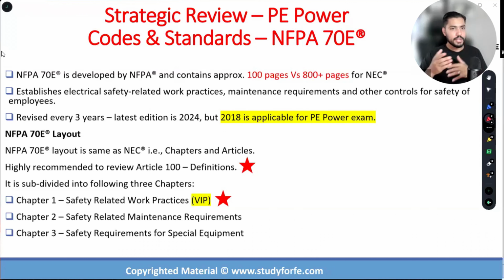130 is work involving electrical hazards, so you have the energized work, shock risk assessment. And the most interesting thing when it comes to calculations within NFPA 70E is that question of whether I can use the arc flash risk assessment, arc flash PPE categories method, or do I have to go through those ugly equations using the incident energy method? We discussed this in a lot of detail in the program as to which method can be used.